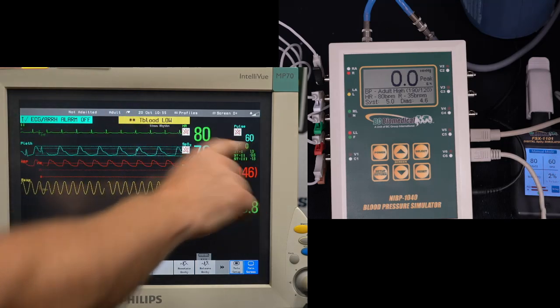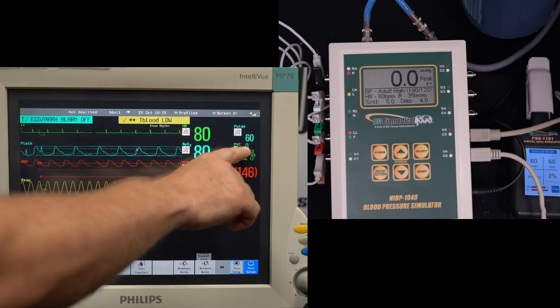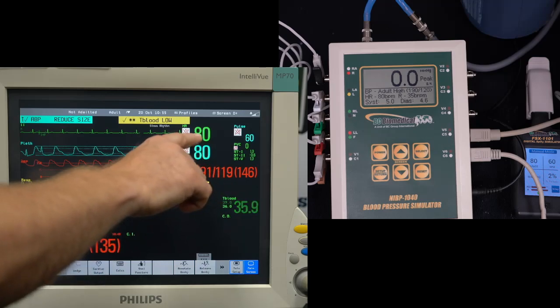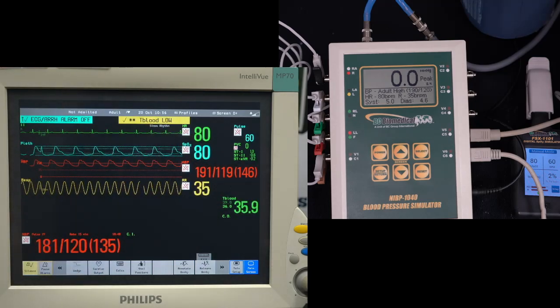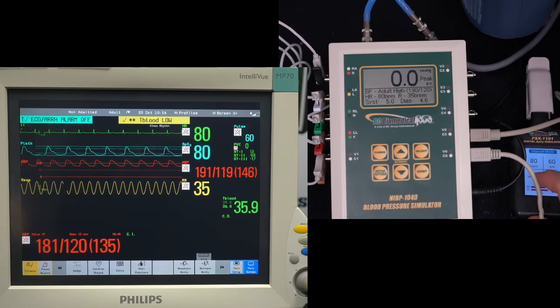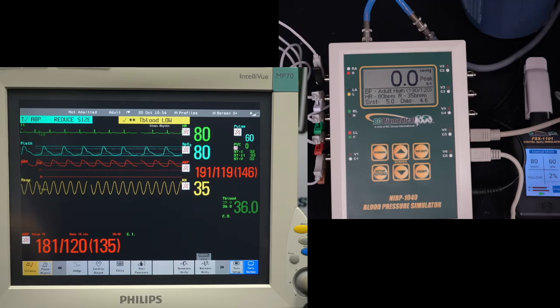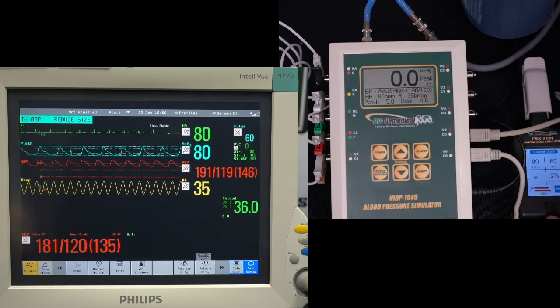So you'll see that it gets a rate of 60 beats per minute from SpO2, and it gets a rate of 80 for the ECG. Some monitors can be confused by that. So that's where we provide this sync cable for the FSX if you want to synchronize the ECG there. It's also easy to select which brand you're testing. Masimo, Nellcor, those are all available right here just by pressing on the screen.